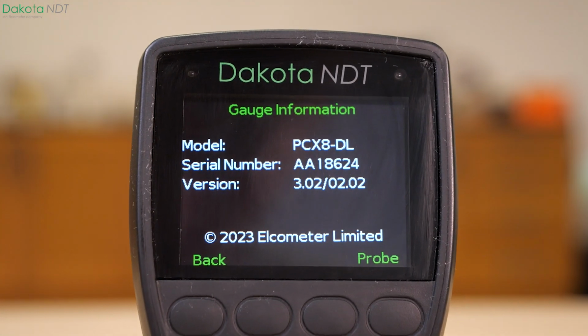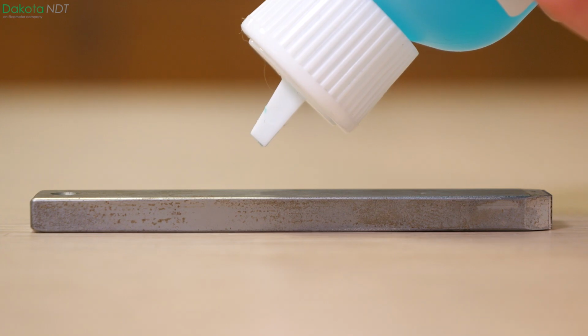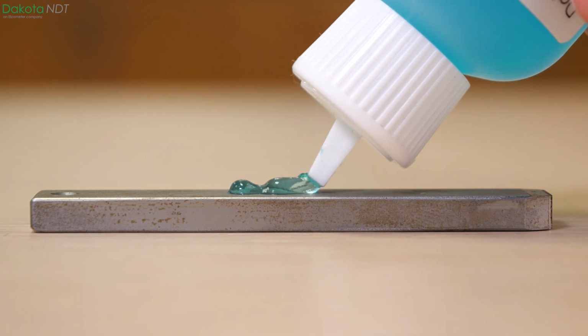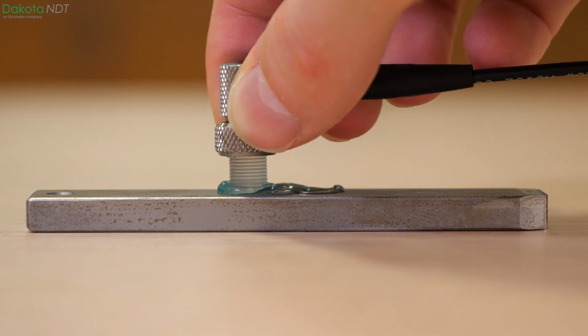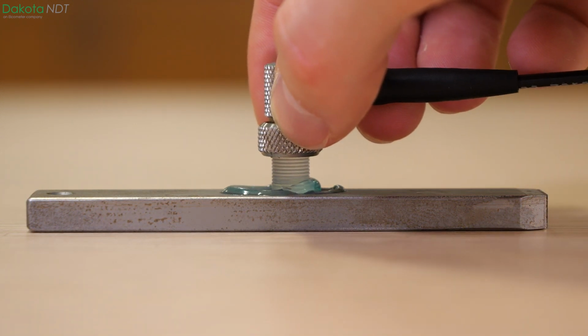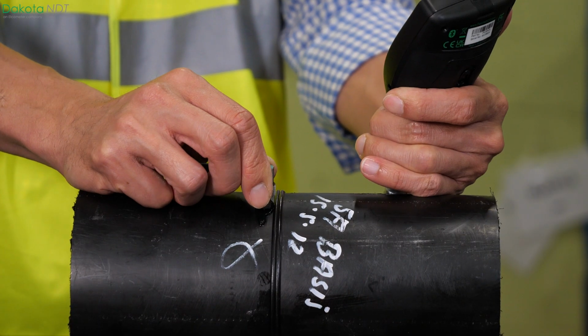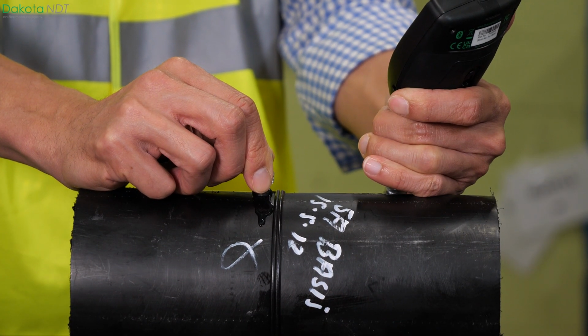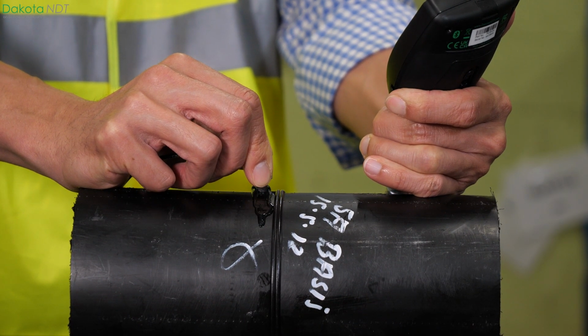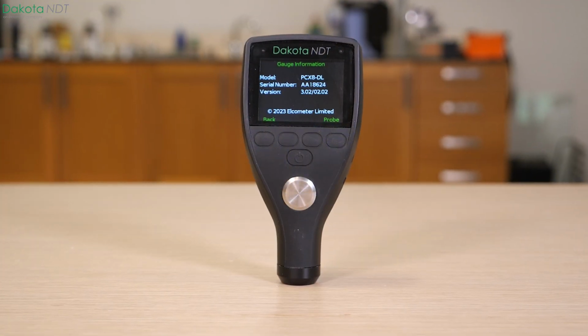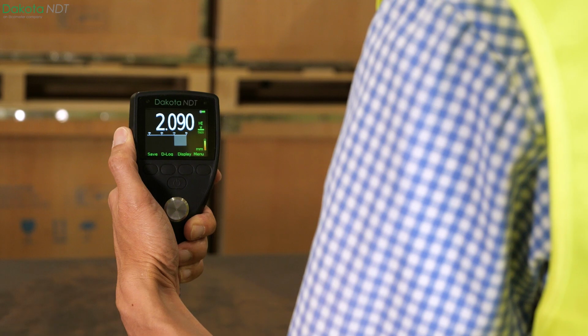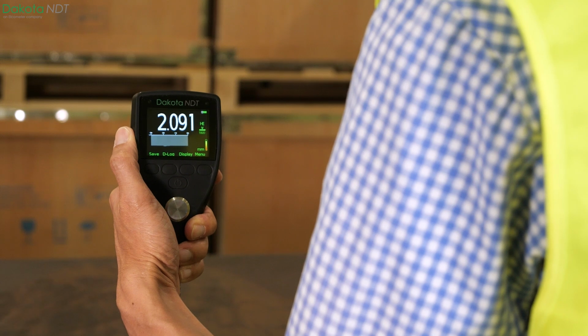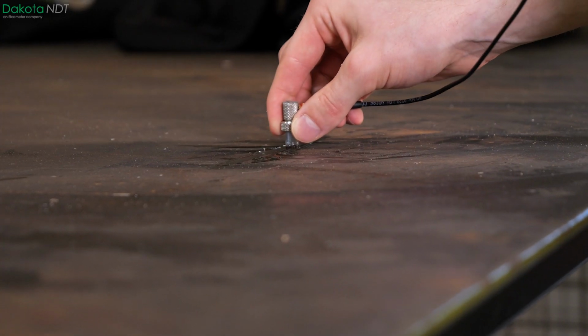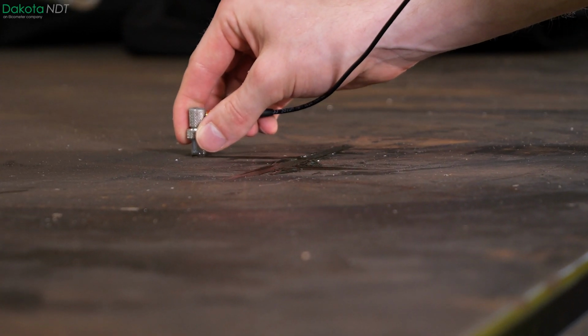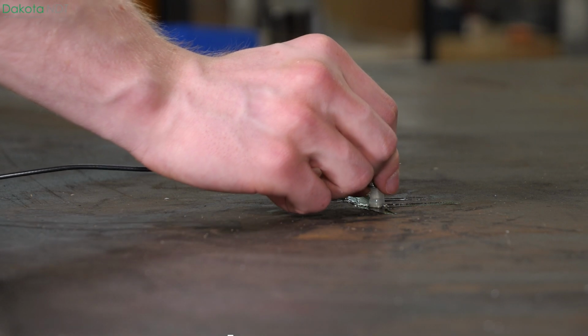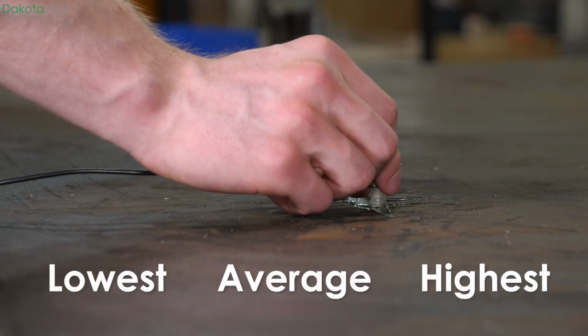The DakotaNDT PCX range has user-selectable measurement rates up to 16 readings per second, otherwise known as 16 Hz, making them ideal for scrubbing across a surface and recording multiple measurements. The DakotaNDT PCX8-DL has scan mode for checking large surface areas. Simply scrub the transducer over the test area, and the gauge will display the average, lowest, and highest thicknesses across the scanned area.